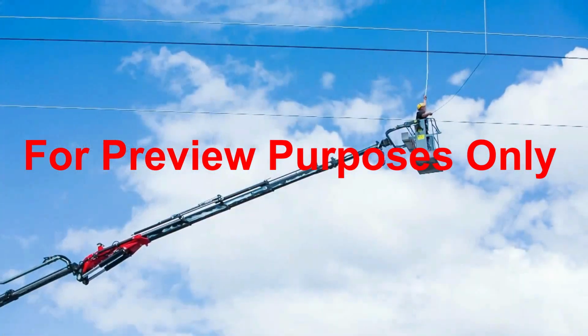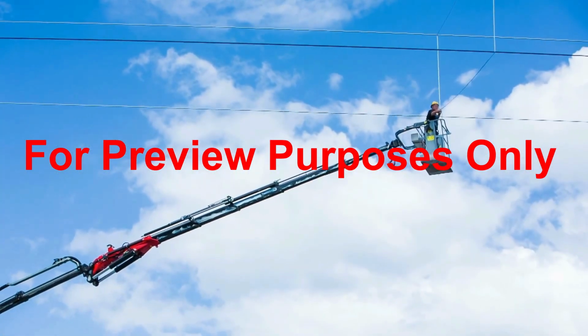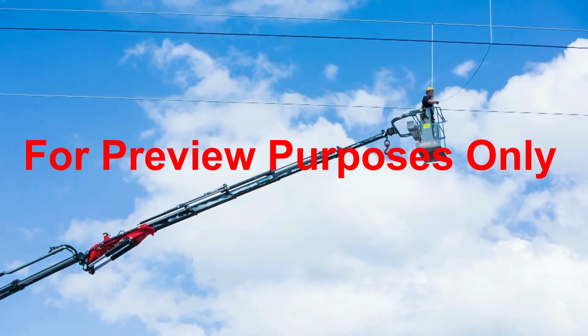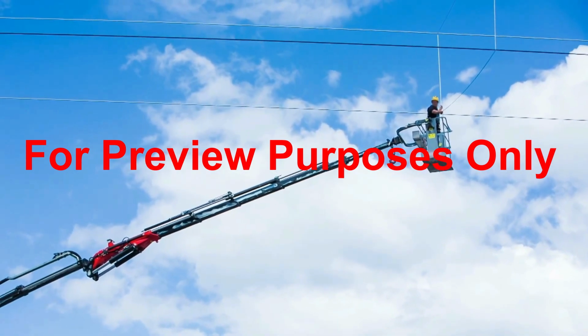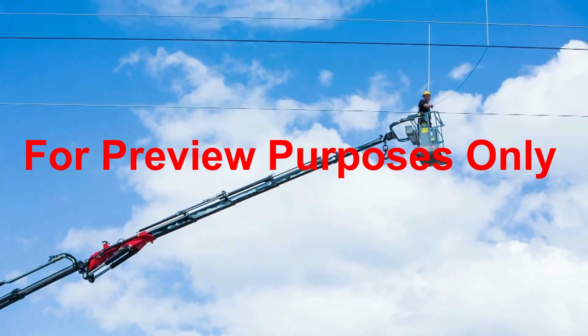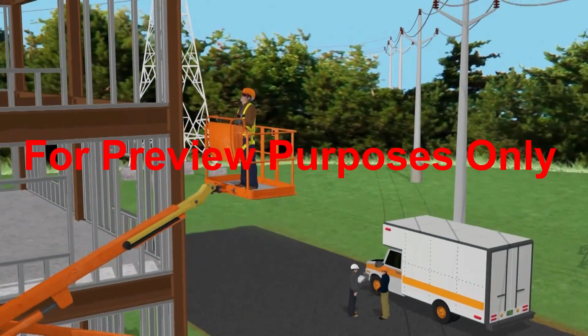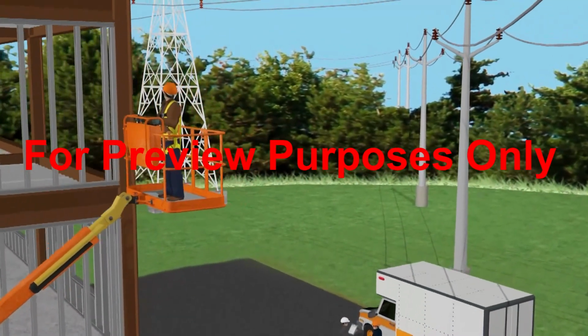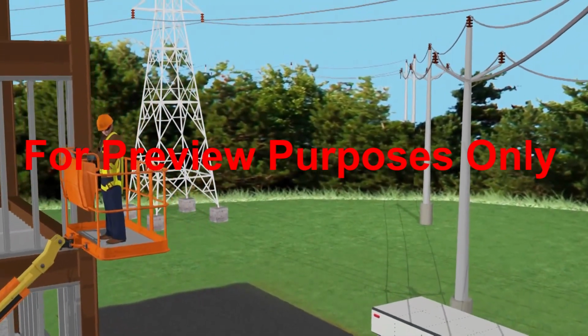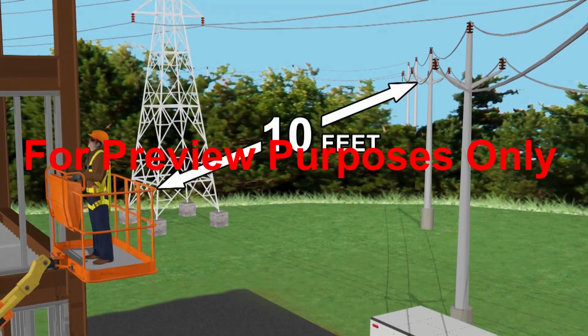If possible, the line should be de-energized. If that's not possible, it's mandatory that you keep a safe distance away from them. OSHA says that if you're not a qualified electrical worker, you and any conductive objects that you're holding should be at least 10 feet away from a line carrying 50,000 volts. You must stay even further away from higher voltage lines.